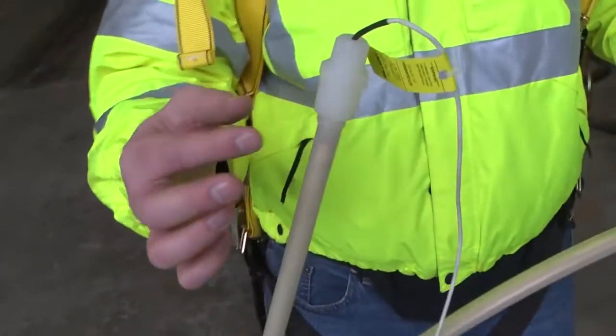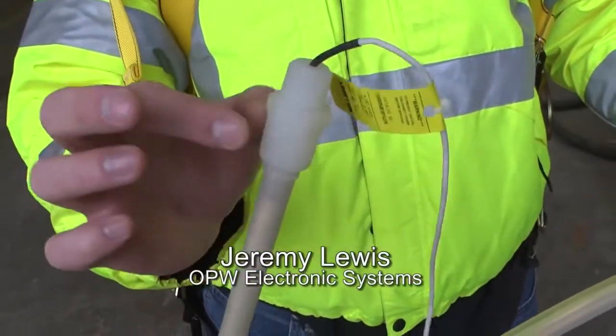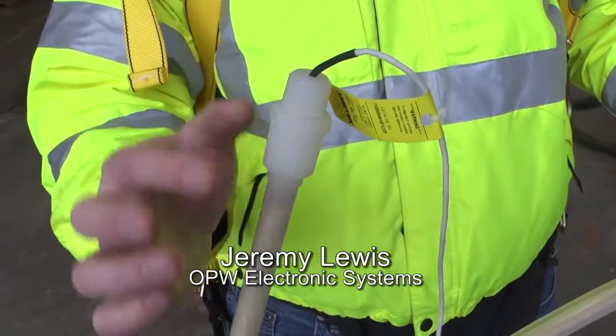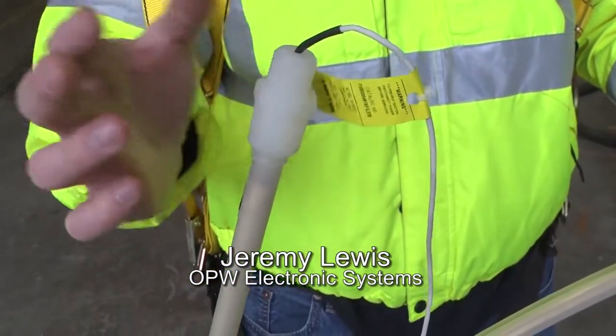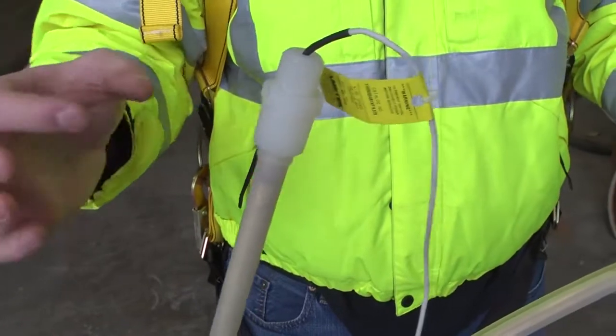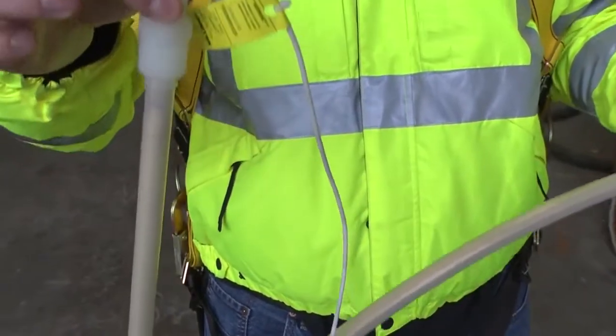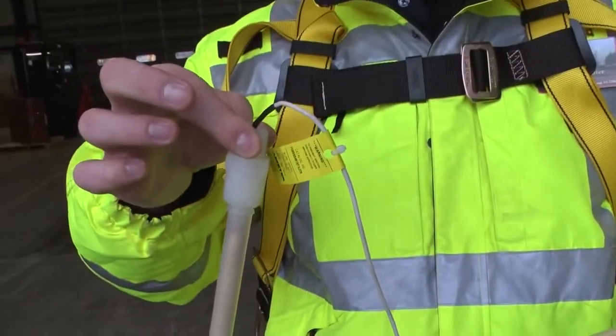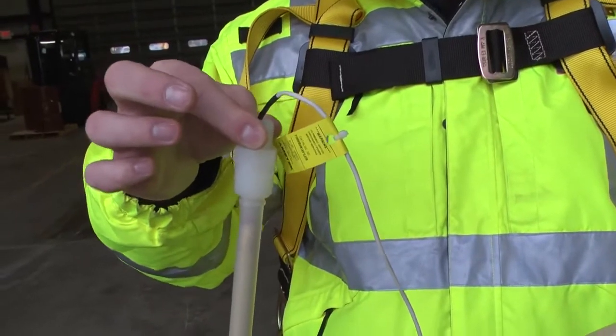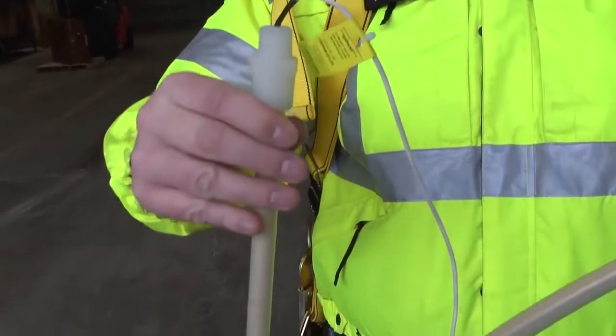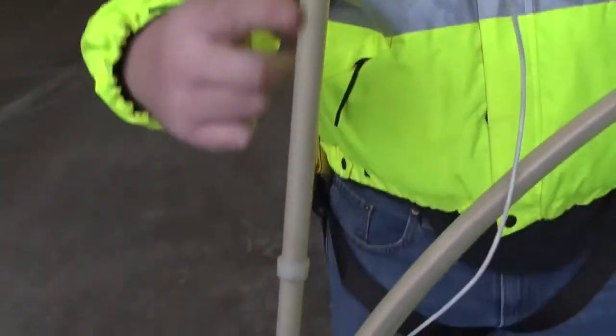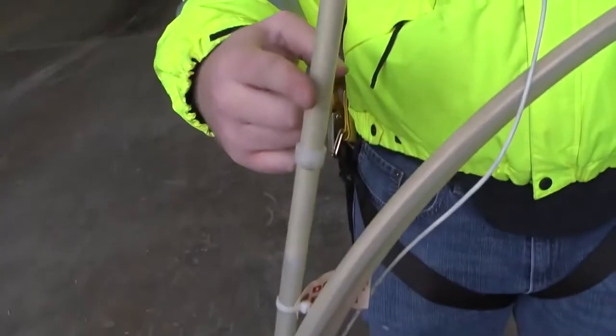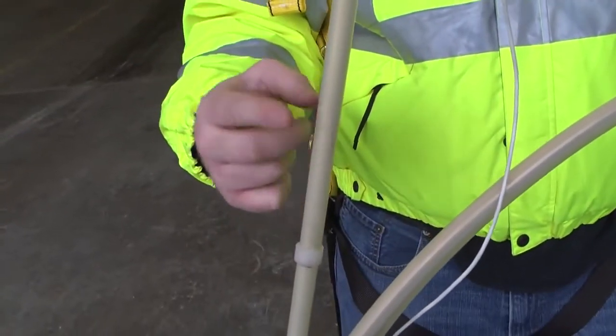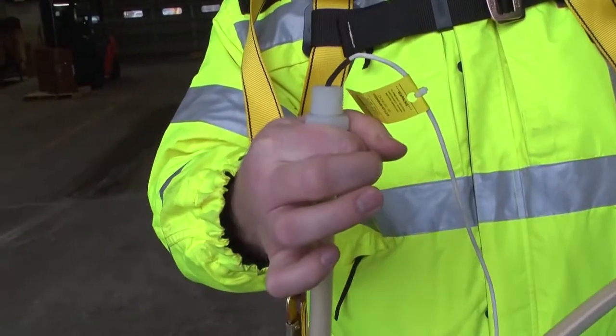On this probe cap here, you have a 3/4 inch support down here. Then you have a 1/2 inch for your junction box. One thing that a lot of technicians do out in the field is they try to hold the probe up from the top here. It causes undue strain on the probe when you're getting deliveries and everything. It causes this piece to flex too much. And once this gets damaged in here, the probe will no longer read. So what you want to make sure you do is that you support the probe from the bottom.